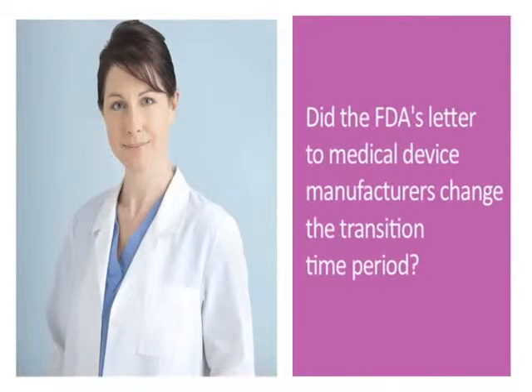The next question is a very important question for all healthcare institutions. Did the FDA letter to medical device manufacturers change the transition time period? This is important to understand. The FDA has given healthcare institutions 18 months, or July 2011, to transition from STERIS System 1 to another legally marketed alternative. However, the FDA also gave medical device manufacturers only 12 months to make the transition to remove STERIS System 1 from their instructions for use, or February 2011.